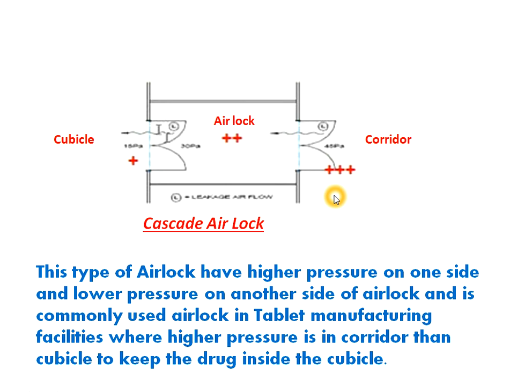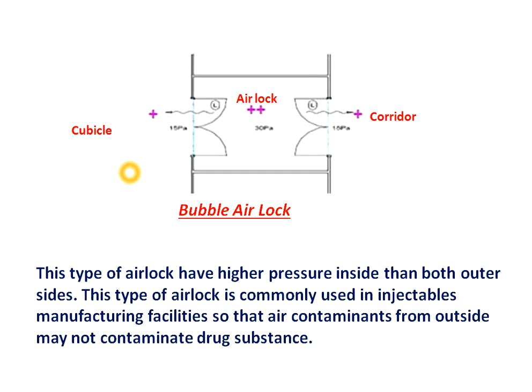Cascade airlock is mostly used in tablet and capsule manufacturing areas because powders are generated there. The second type is bubble airlock. As shown in the diagram, bubble airlock has maximum pressure compared to its surrounding areas — both the corridor and the cubicle. The corridor is indicated by a single plus and the airlock by a double plus. For example, if the airlock has 30 pascal pressure, then the corridor will have 15 pascal and the cubicle will also have 15 pascal.